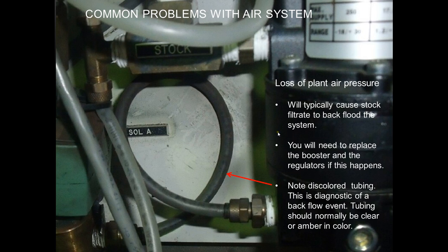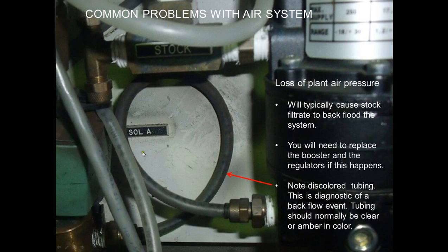When you lose air pressure and you get a stock blowback, there are some things that you can see immediately. One of the first things that I tend to look for is this little loop of tubing inside the Drainac enclosure, connecting the intake regulator on the right with the solenoid valve on the left there. When you get a blowback, this inevitably will get discolored because it captures a lot of debris.